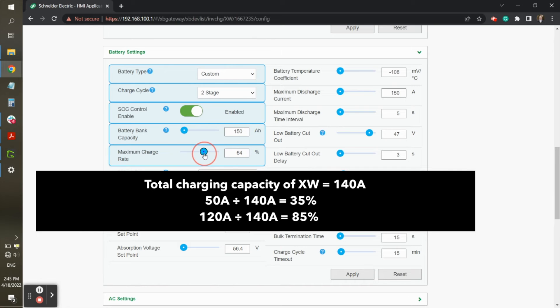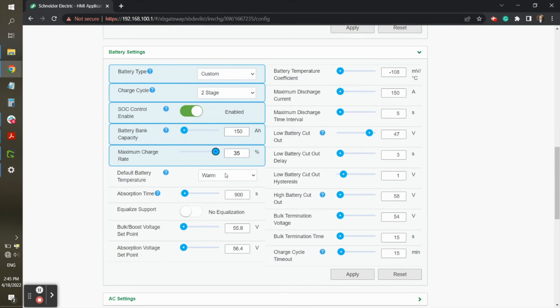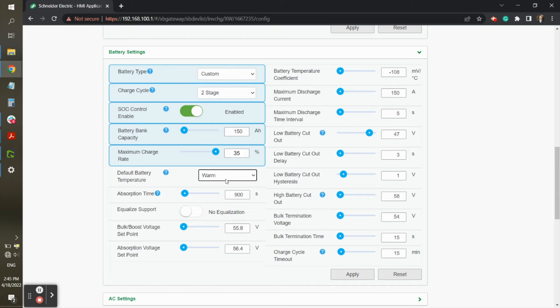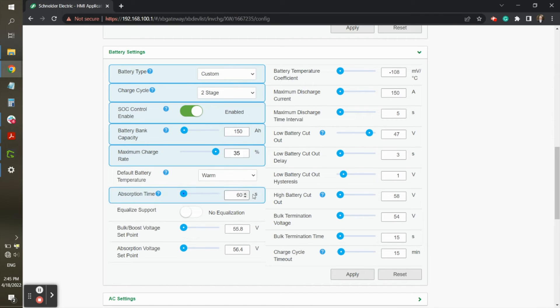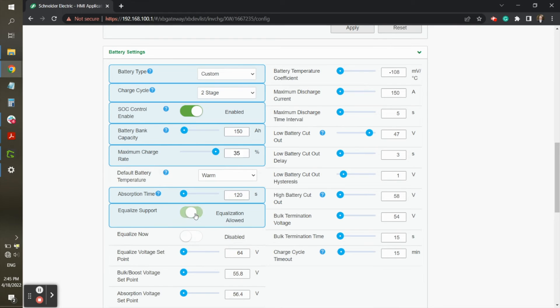This, of course, will depend on how many batteries there are in the bank and what warranty profile the customer chooses. Battery temperature can be left at warm. The temperature sensor should be disconnected and not used with the Kilovolt batteries. Absorb time should be set to 2 minutes, or 120 seconds in this case. Equalization should be disabled.